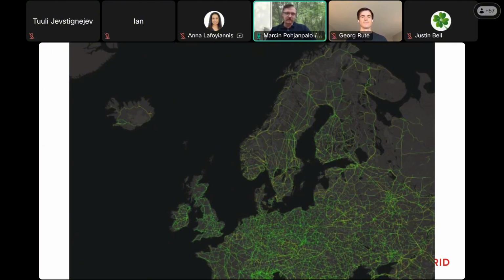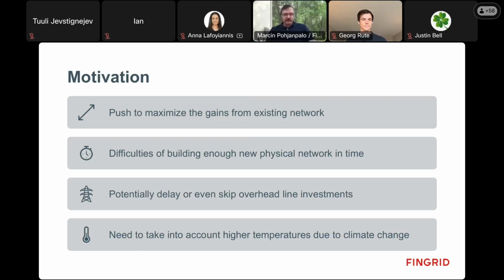That's one of the reasons why you really want some kind of ambient adjusted or dynamic line rating system here. Nowadays, as we get more wind power and solar power plants, we're approaching close to 10 gigawatts of wind power already. We're not really able to physically build enough network to connect it all to the grid, because most of our wind power production is up north or on the western coast, while most of our consumption is in the south. So it's hundreds of kilometers we need to transfer the electricity, and at the same time there's a strong push to maximize current grid usage, because we need to get more value for the money spent. One idea is that even if this only helps delay some investments, it would already be more than worth its value, and in theory it could even help skip some investments.